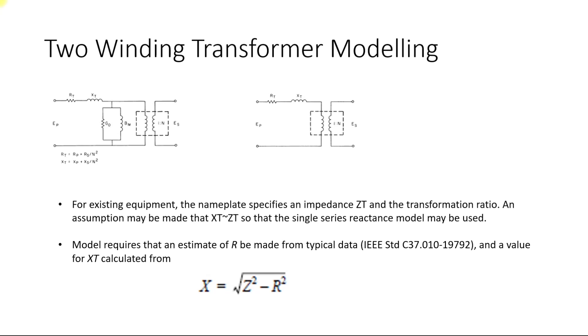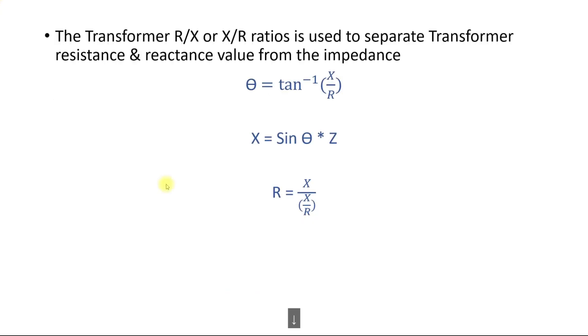To calculate R and X individually, you need the X/R ratio, which is typically provided on a transformer datasheet. If the Z value and X/R ratio are both available, you can calculate them separately using: theta equals tangent inverse of (X/R), X equals sine(theta) times Z, and R equals X divided by (X/R). Using these formulas, you can individually calculate R and X from Z and the X/R ratio.